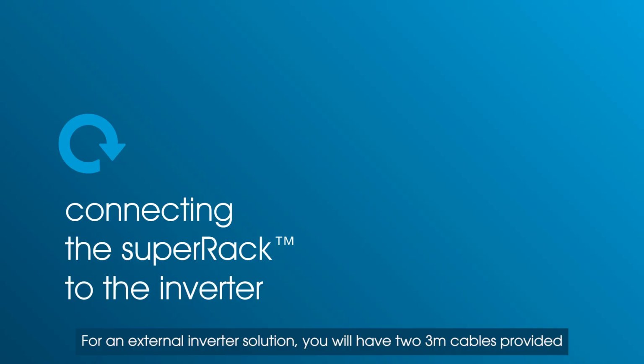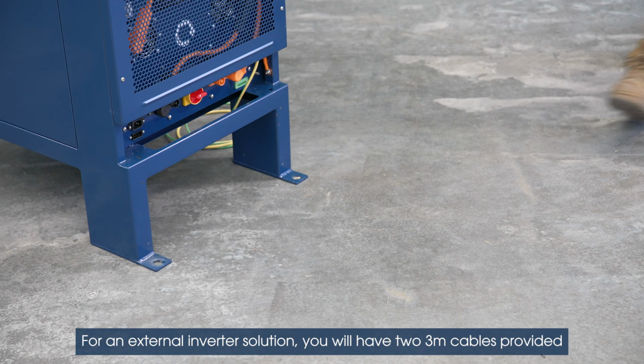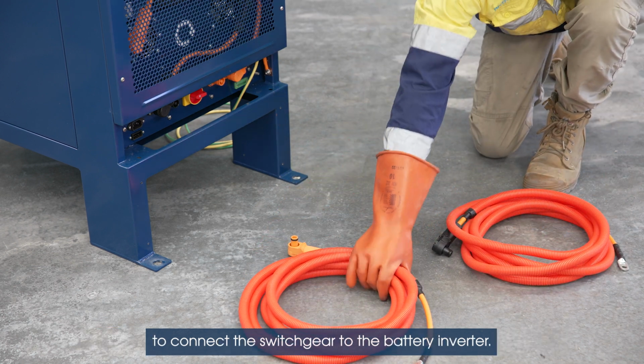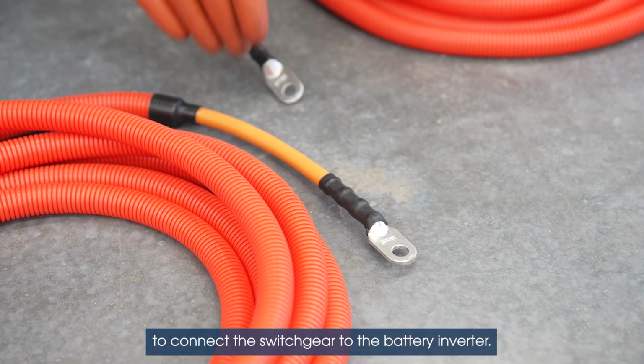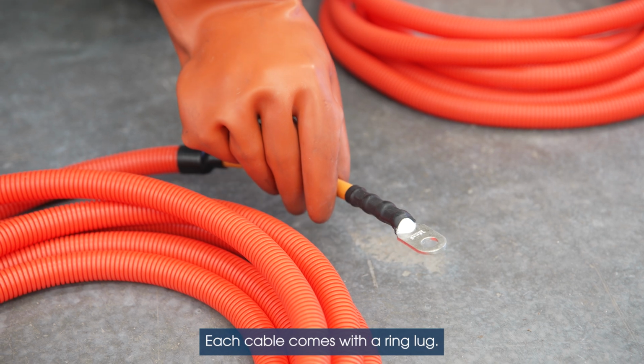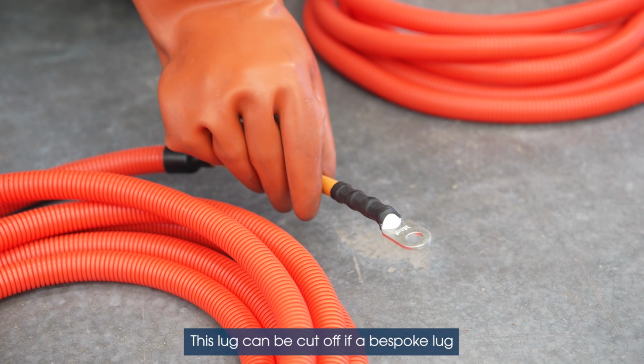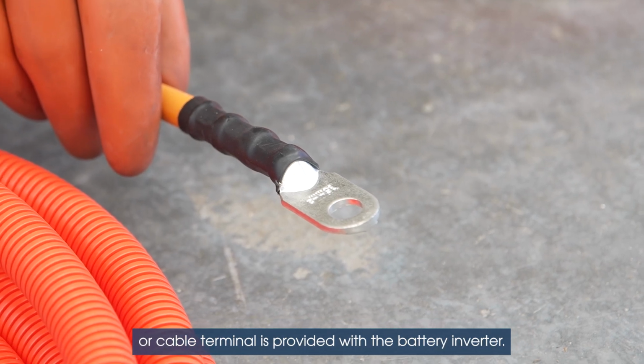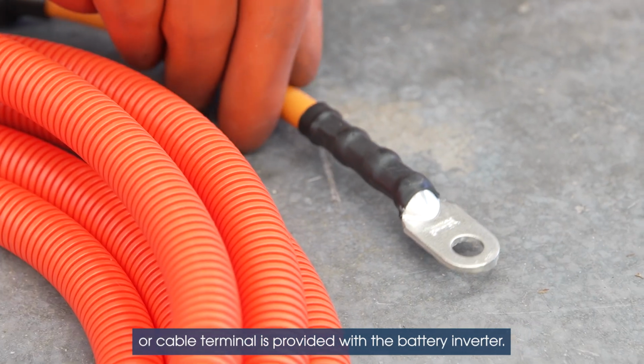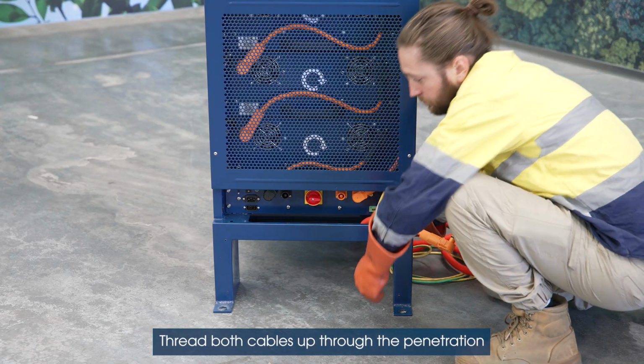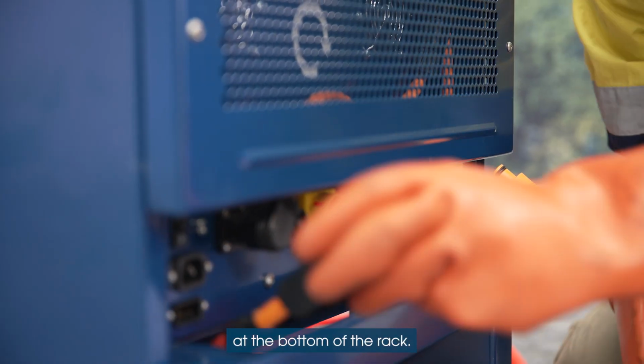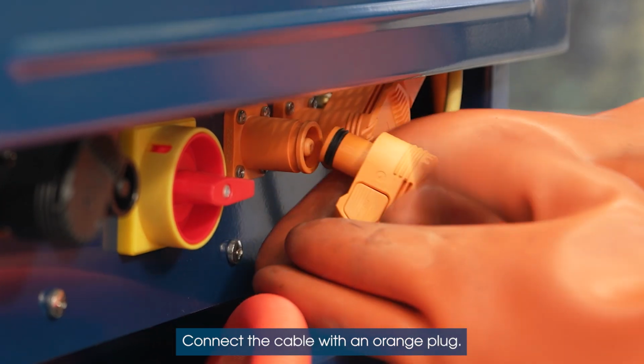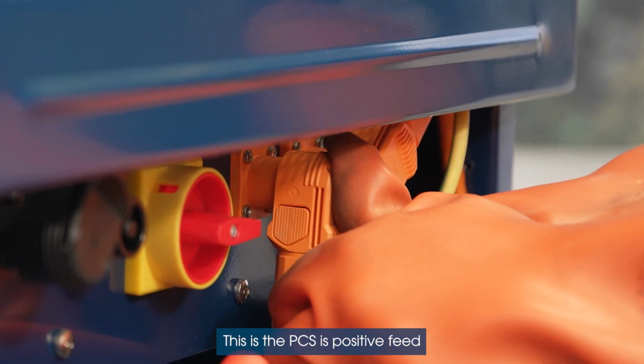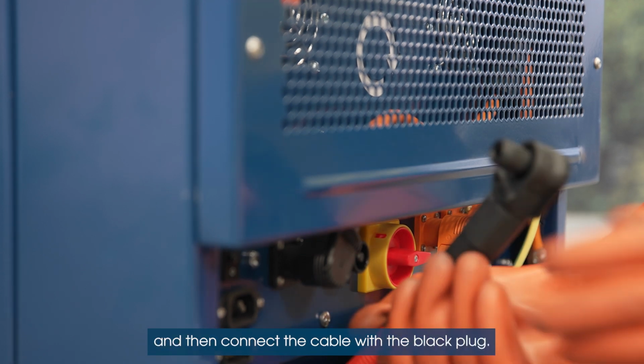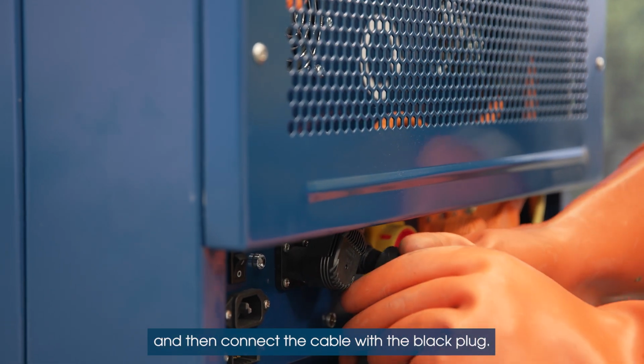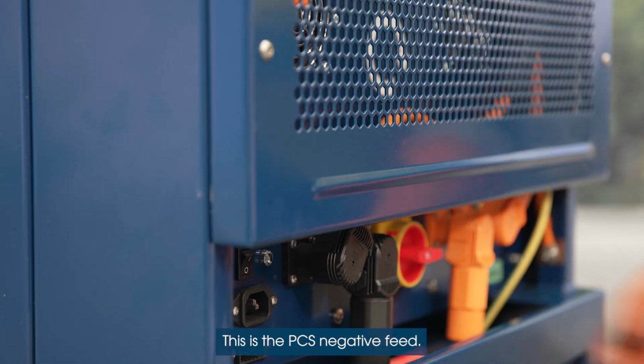For an external inverter solution, you will have two 3-meter cables provided to connect the switchgear to the battery inverter. Each cable comes with a ring lug. This lug can be cut off if a bespoke lug or cable terminal is provided with the battery inverter. Thread both cables up through the penetration at the bottom of the rack. Connect the cable with an orange plug. This is the PCS positive feed. And then connect the cable with the black plug. This is the PCS negative feed.